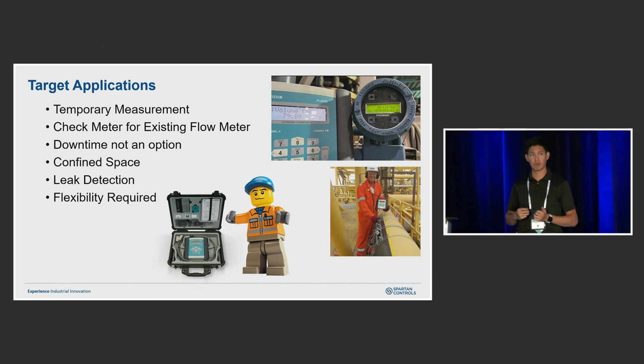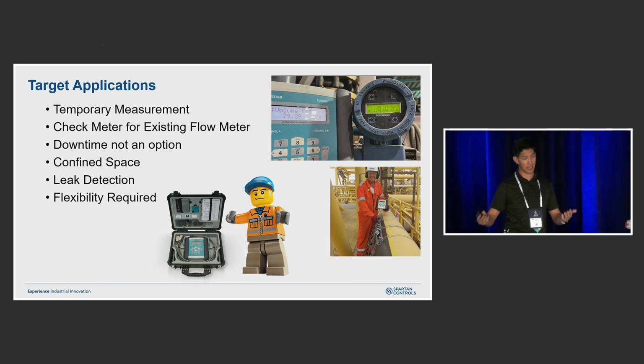So what are we trying to look for? What we're trying to do with this flow meter is anytime we need a temporary measurement, this is a great application for that. You just want to get an idea of what's happening in a particular line. If you have a flow meter you don't trust, here's another option we can put on just to verify it. So there's an example of a clamp-on ultrasonic compared to a magnetic flow meter. The output's quite close, so we know we have a lot of faith in the magnetic flow meter.